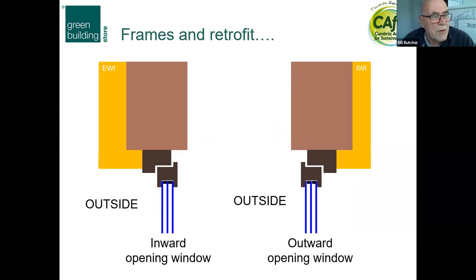Let's talk about retrofit in principle. With internal wall insulation, we don't go above a 0.35 U-value because we don't want to raise the risk of interstitial condensation by making the wall too cold — particularly worrying about timber floor joists into walls. With external wall insulation, we're actually taking the risk out of it, making the wall warmer, so we can put on far more and might be going to a U-value of 0.15 or even down to 0.1. This determines the inward or outward window strategy.